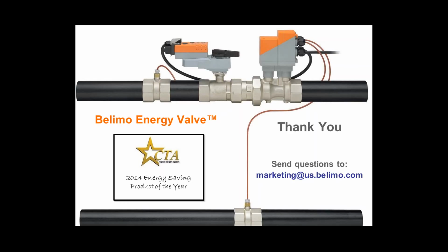It's when it gets about a degree or so below that value. So we're at 12 degrees, now we're at 11 and a half, we're still listening, we get down to around 11, and I don't remember the exact number, but we could find out. At that point, the Energy Valve would suspend the direction of the automation system and start reducing the flow to push that delta T back up. But the rest of the day works just like any other high-quality pressure-independent valve.